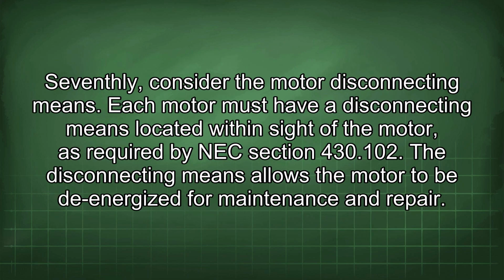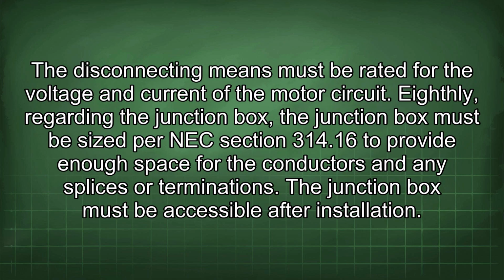Seventhly, consider the motor disconnecting means. Each motor must have a disconnecting means located within sight of the motor, as required by NEC Section 430.102. The disconnecting means allows the motor to be de-energized for maintenance and repair. The disconnecting means must be rated for the voltage and current of the motor circuit.